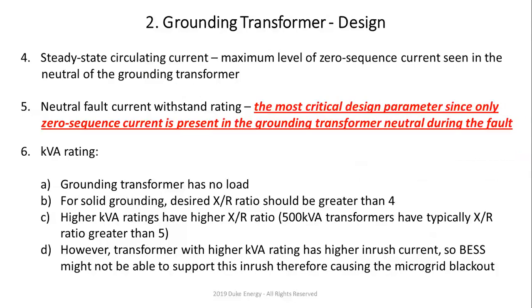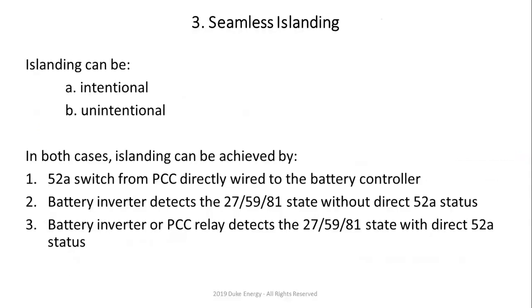Because what you're going to see, if you don't have the proper X over R ratio, you are going to reduce the available fault current. And over here, as you can probably know, DERs already have very low currents. So you definitely want to have a solidly grounded system. However, the biggest challenge is how you manage the inrush current so that the battery energy storage system can actually keep the microgrid alive during the transition, right? We're going to talk about it later because this is probably the most challenging part.